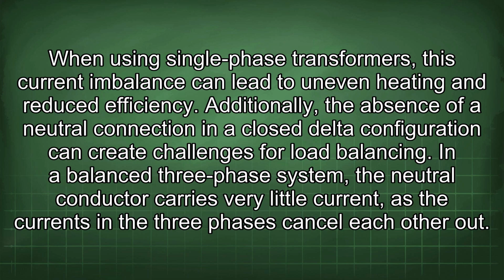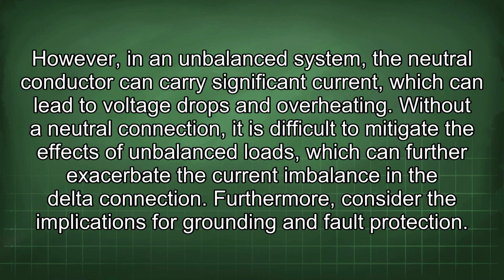Additionally, the absence of a neutral connection in a closed delta configuration can create challenges for load balancing. In a balanced three-phase system, the neutral conductor carries very little current, as the currents in the three phases cancel each other out. However, in an unbalanced system, the neutral conductor can carry significant current, which can lead to voltage drops and overheating. Without a neutral connection, it is difficult to mitigate the effects of unbalanced loads, which can further exacerbate the current imbalance in the delta connection.